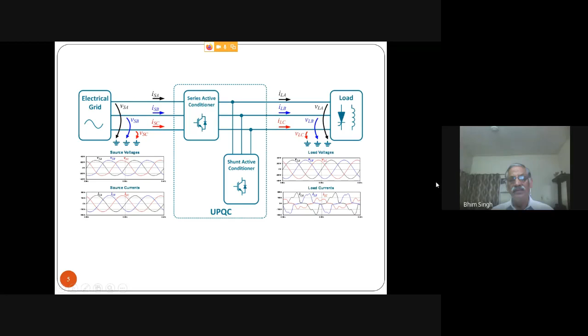This device certifies both the grid and the load, and we call it a unified power quality conditioner or compensator, whatever name you give—different names are used in the literature. We expect the grid's current to be sinusoidal even though the voltage may be unbalanced or distorted, but voltage unbalance or distortion does not mean the current should not remain sinusoidal and balanced. Similarly on the load side, whether the load current is unbalanced or harmonic, the load voltage should still be sinusoidal and balanced.